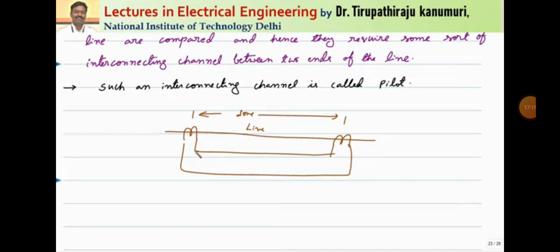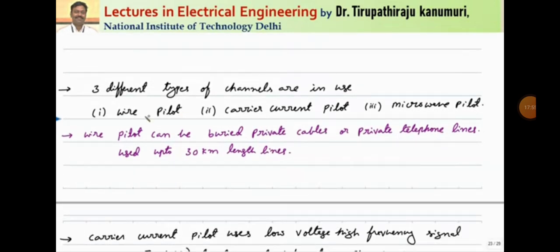One scheme is to transmit through the same transmission line using a different frequency compared to the supply frequency — this is the carrier current scheme. Another option is to transmit using microwaves. So, either microwave transmission or carrier current transmission can be used. There are three different categories: wire pilot, where physical wire is used; carrier current pilot; and microwave pilot. The wire pilot can use buried private cables or private telephone lines and is limited to up to 30 kilometers.